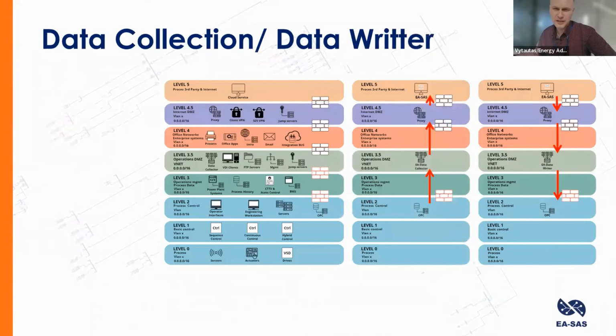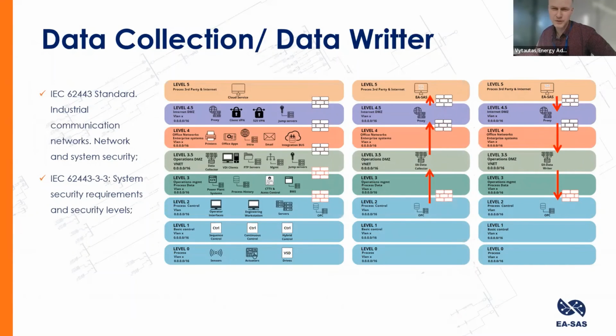For the data collection and write software, we solved this issue according to the IEC 62443 standard about network and system security in industrial communication networks. If you have an OPC firewall, we install the data collection software on level 3, and through the proxy we send data to level 5. It is in the cloud, and the command-back goes on a separate path. These paths are configured absolutely differently, and at the software level too. From the SaaS cloud, we send data to the level 3 data writing software, Energy Advice production, and we write data to OPC. From the OPC, it could be, for example, a Profibus gateway to Modbus, or a Profinet gateway, or Modbus, or whatever, or controllers.